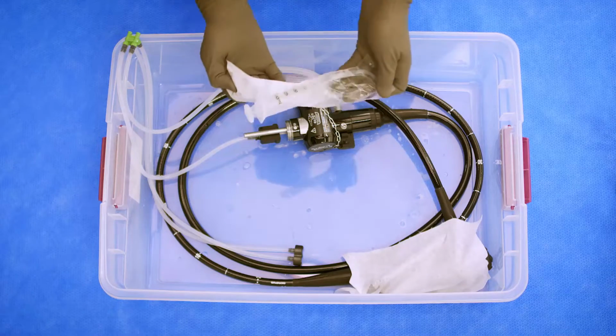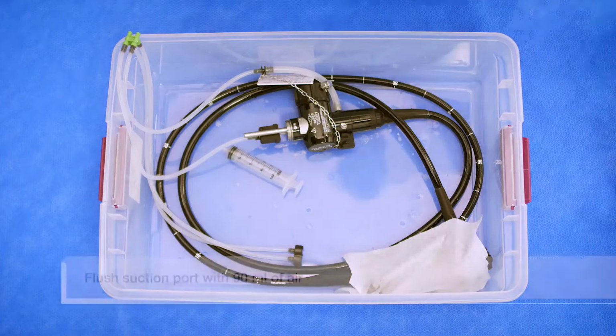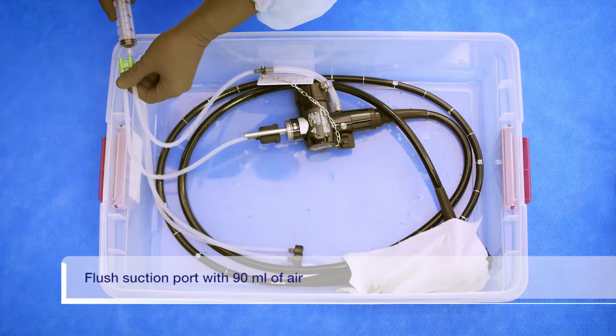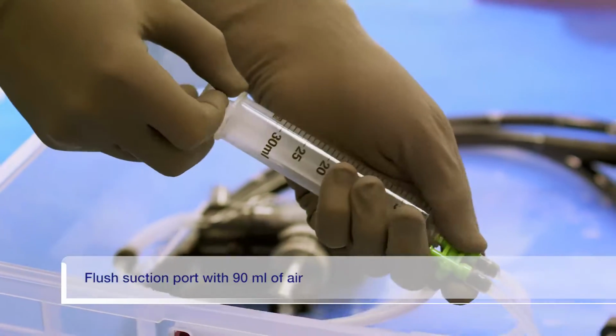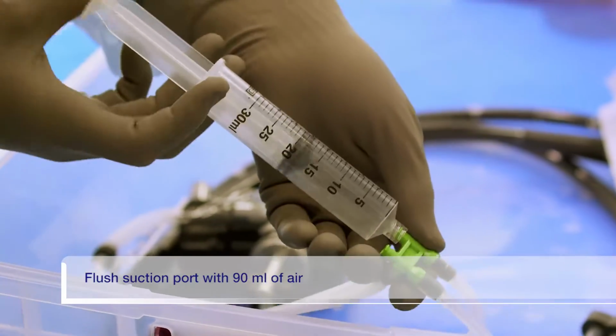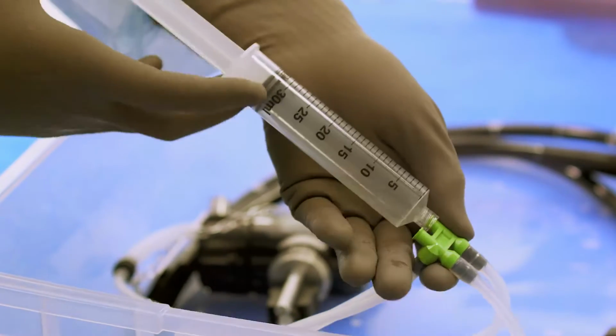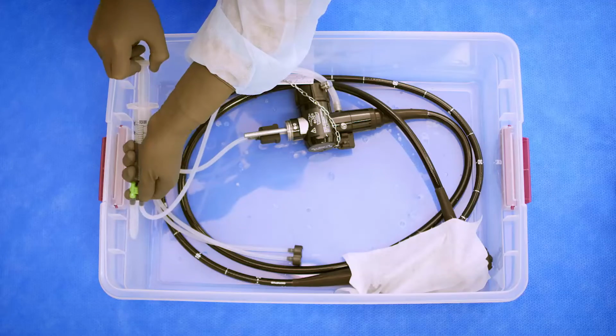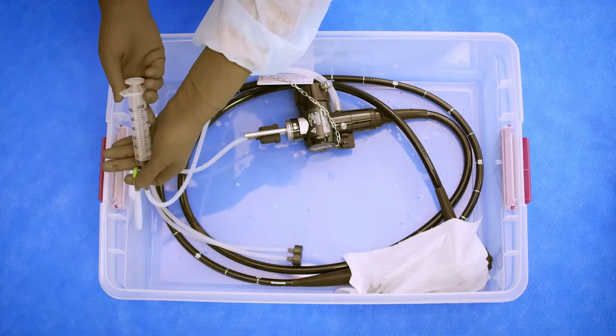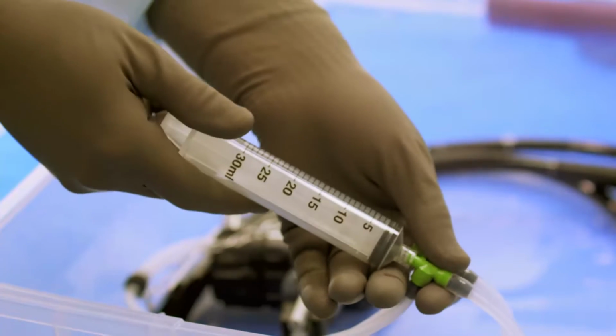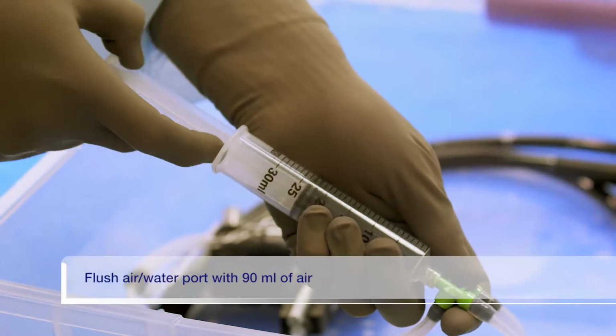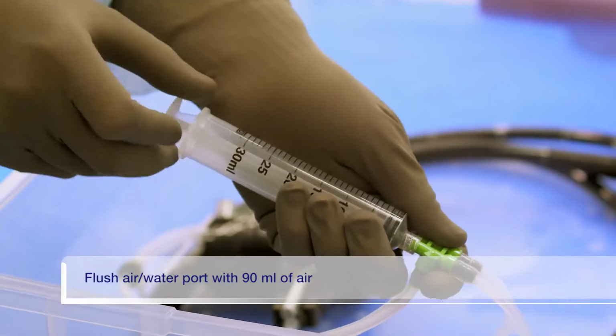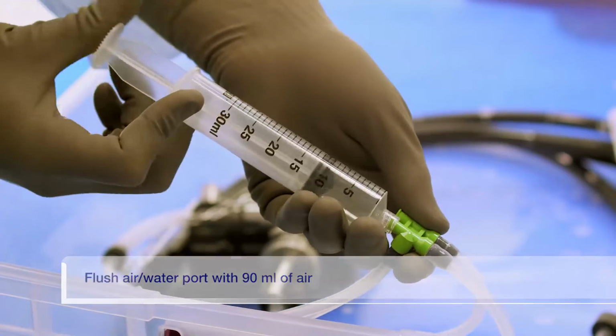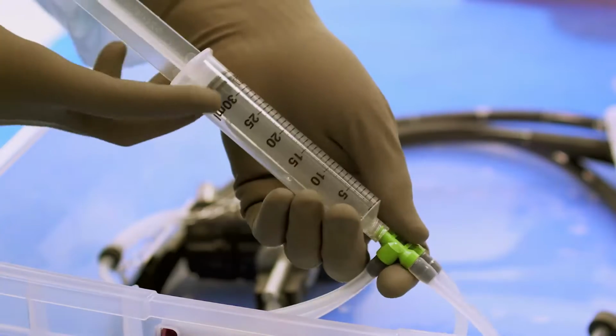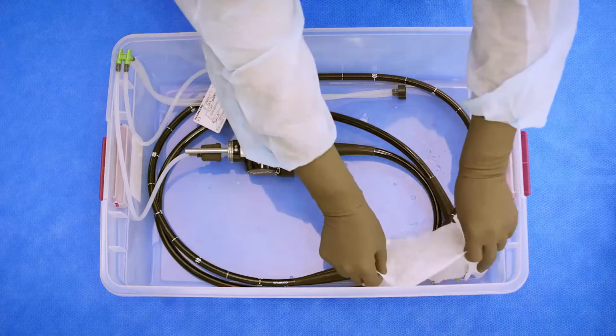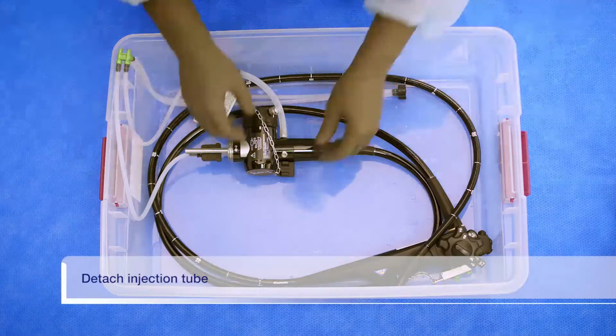Attach the 30 milliliter syringe to the suction channel port of the injection tube and flush the suction channel with 90 milliliters of air. Move the 30 milliliter syringe to the air-water channel port of the injection tube and flush the air-water channel with 90 milliliters of air. Remove the cloths from the endoscope and detach only the injection tube.